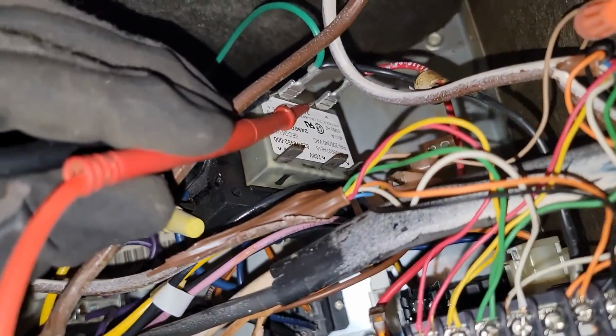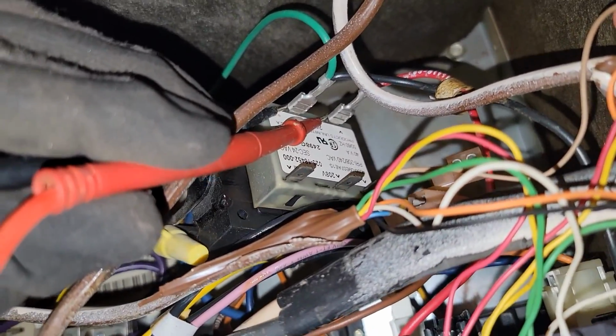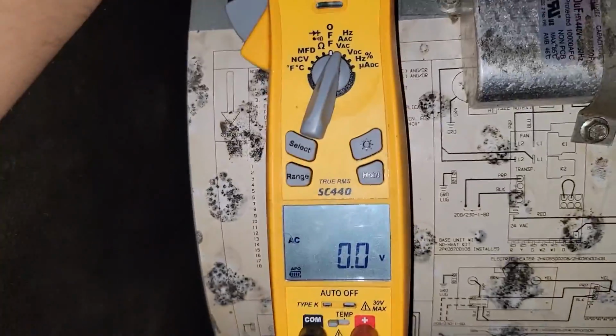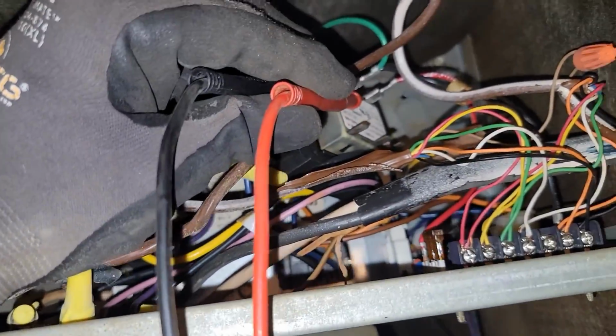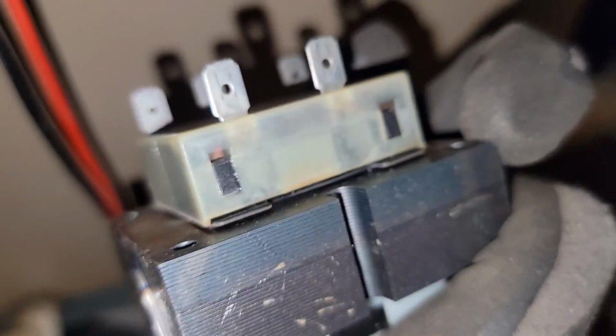Checking the secondary, I've got 0 volts. You can see that we're on the 24 volt side there. No voltage. Bad transformer. Got to replace the transformer. Bad transformer. Kind of looks a little black underneath that plastic. I need to see what caused it.